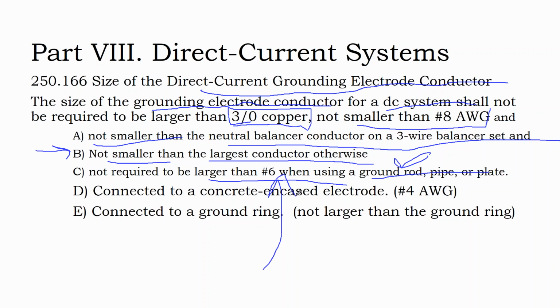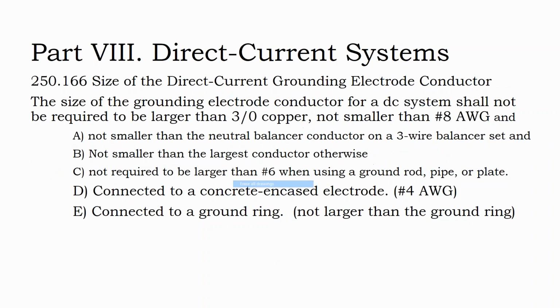Otherwise, you might be sizing your grounding electrode conductor to be the same size as your largest conductor. On a residential system, that might be a number 10 wire, but on a commercial system where you're using combiner boxes, that could get up to something much larger. Here we go.